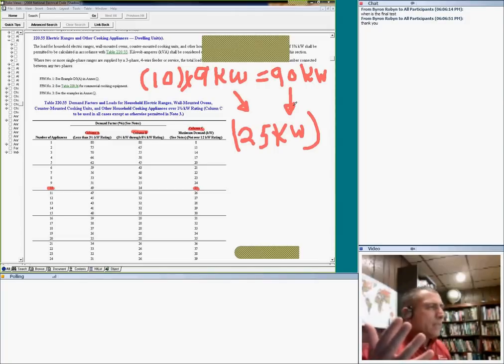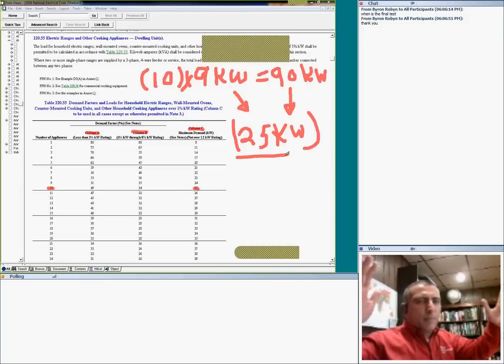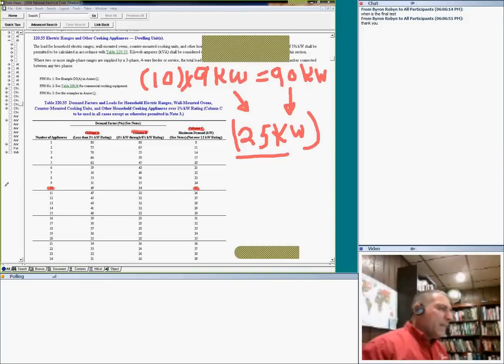And the reason for this is, what's the likelihood that you have 10 apartments and all of them are using their range at full capacity, every single eye, every single oven, every single cooking burner on the range fully on at the same time? Gerald will say that's Thanksgiving. The likelihood of that is very low, it's a chance that we can take, and that's why they came up with the 25 kW. I don't have to size for 90 kW, and my service will not be huge. They demand all the way down to 25 kW.